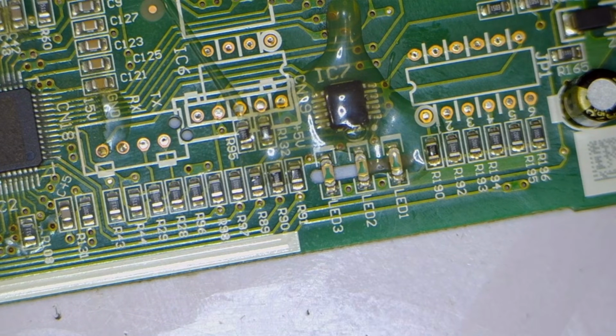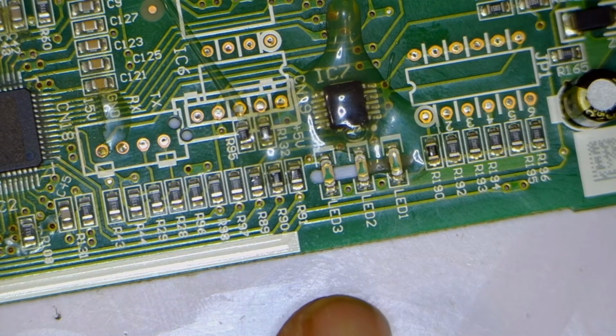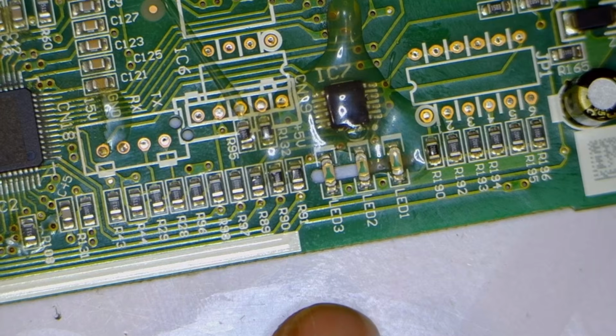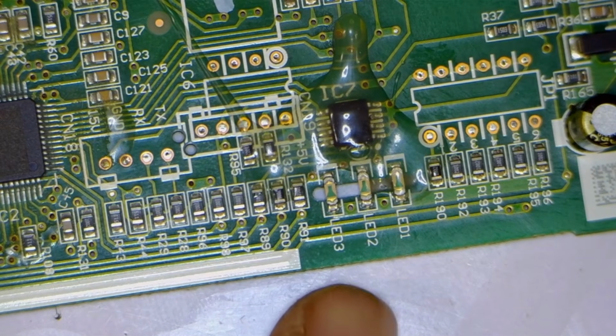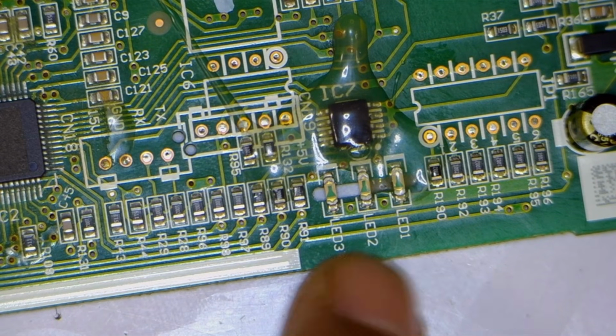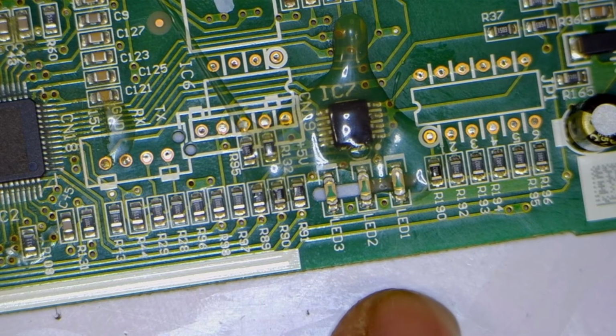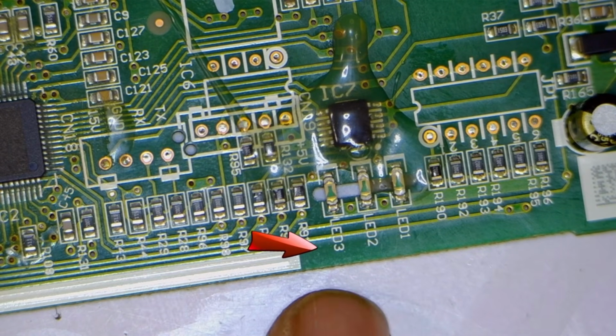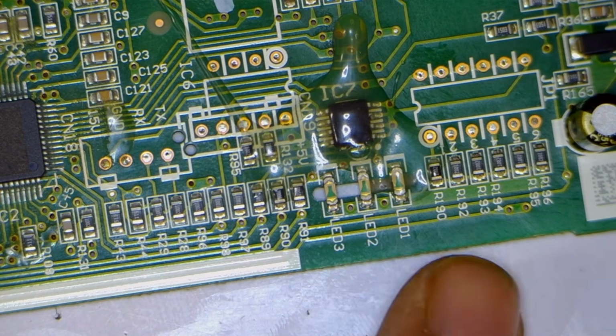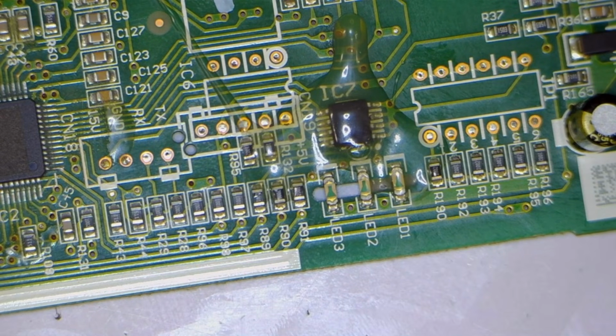Normally, when there is an F1 error, the LEDs show up immediately. However, no LED error blinking is happening, which means the PCB is completely fine, and until now there has been no problem. It is waiting for the serial communication, and since its connection with the indoor PCB has not been made, it will keep trying. After a while, LED 3 and 2 will become stable, and LED 1 will start blinking. We will wait as well, and here, LED 3 and 2 have become stable, and LED 1 has started blinking.